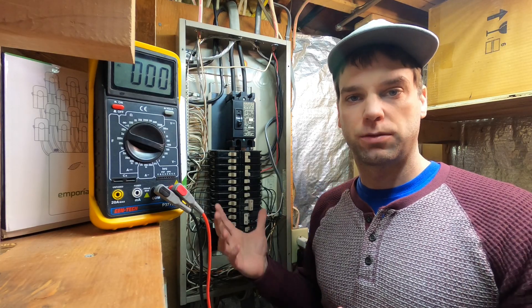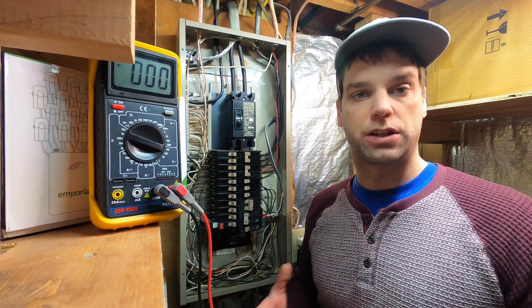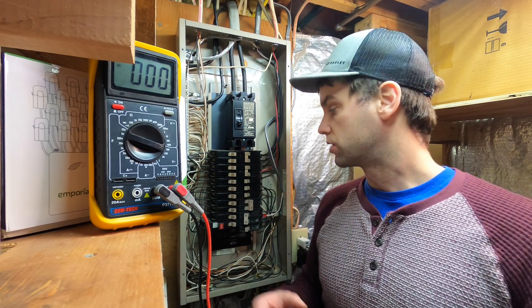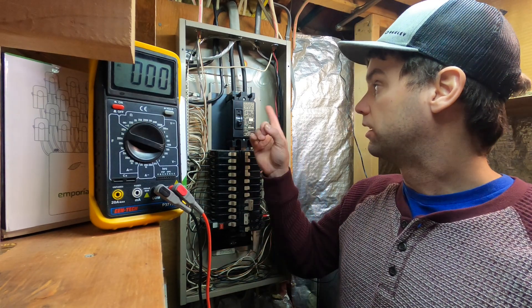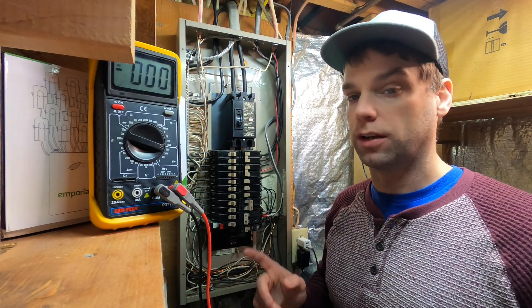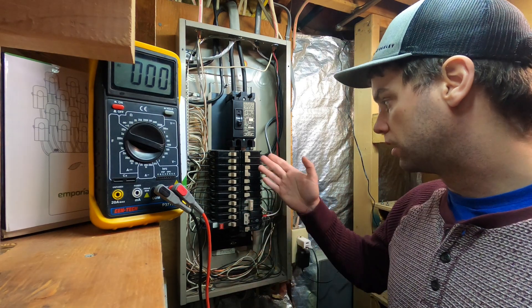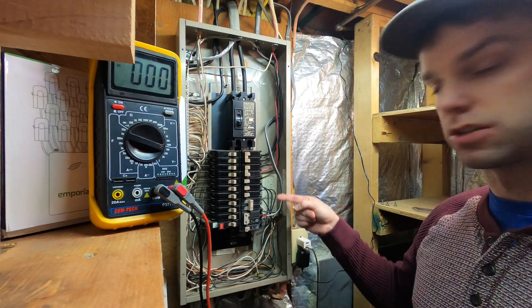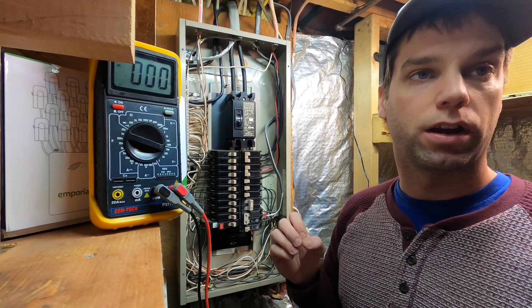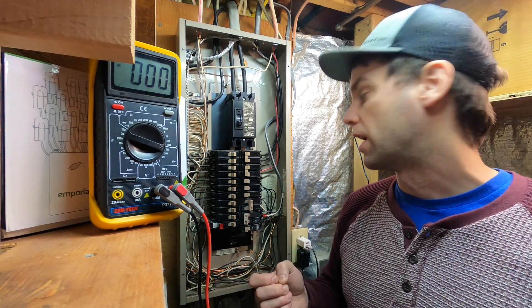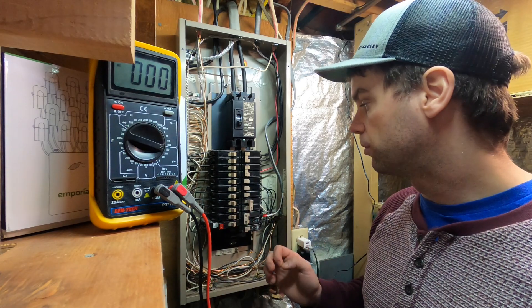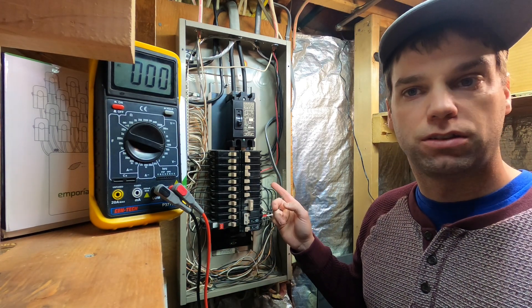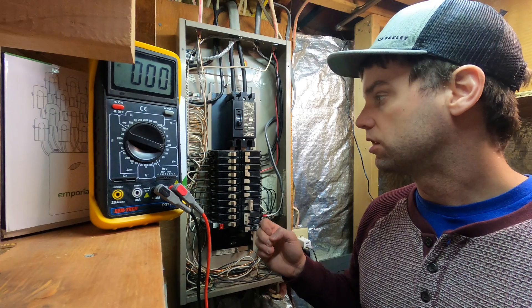All right. So we've got our protective cover off of our main panel. And what we're going to do is we're going to check and make sure that our voltage is turned off to these breakers and confirm that it is still on here on the main. So we've got to be really careful of the main. So in order to check your voltage against one of these breakers, each one of these breakers has a screw on them. And that screw along the side is going to be where you can check for power. You can also check along the wire, but if it's installed properly, there should be almost no bare wire visible. It should be insulation there.